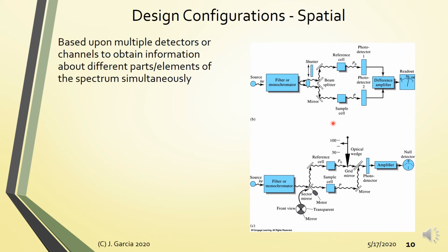So that's one advantage of your double beam design, and this is the reason why most spectrophotometers nowadays include this type of design. If you're using a non-dispersive instrument, you need to use multiple filter systems. So there are separate filters for the reference and the sample cell.